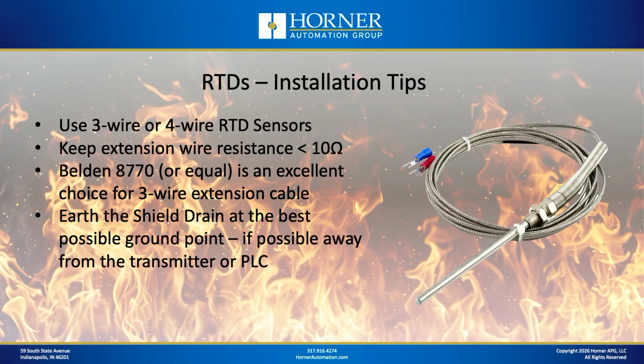You do want to keep the resistance of your lead wire connecting your measuring instrument and the probe itself at 10 ohms or below. And the easiest way to do that is to use just a decent extension wire for that purpose. So Belden 8770 or equivalent, for instance, is a 3-conductor cable for a 3-wire RTD, but it's not specific for RTDs, but it's 18-gauge wire, and its resistance per 1,000-foot rating makes it an excellent choice for use with RTD sensors as an extension wire. So that's one I can definitely recommend for you, especially if you have any distance involved, okay?